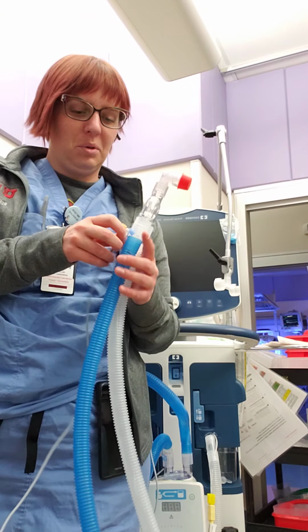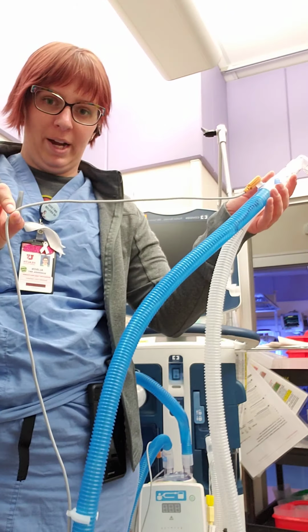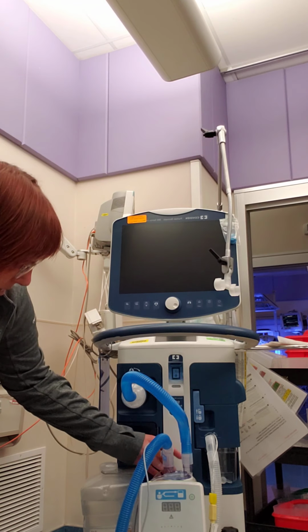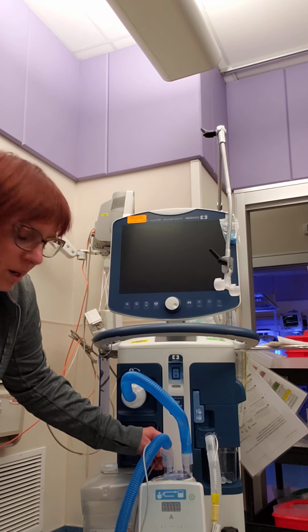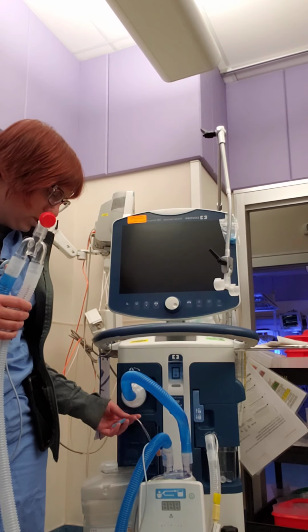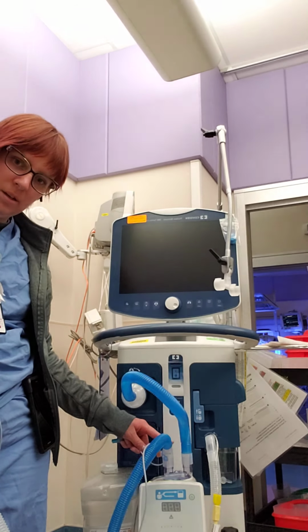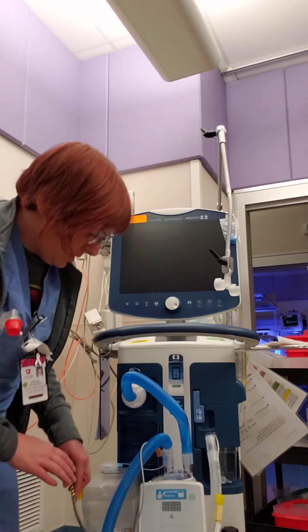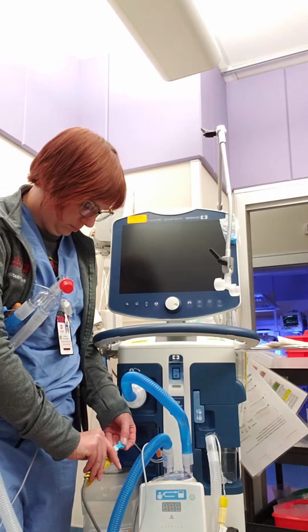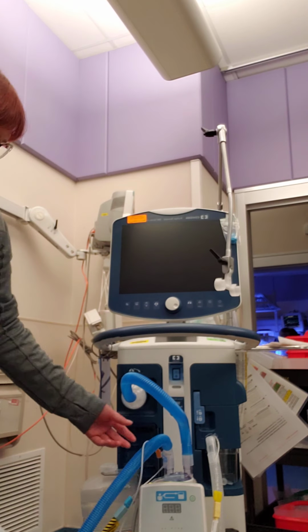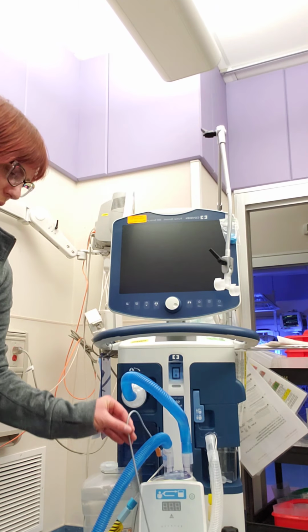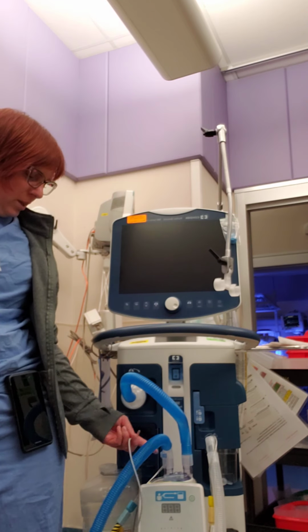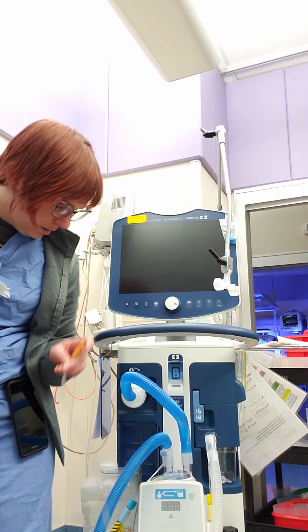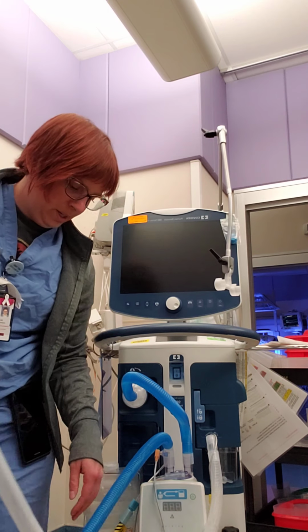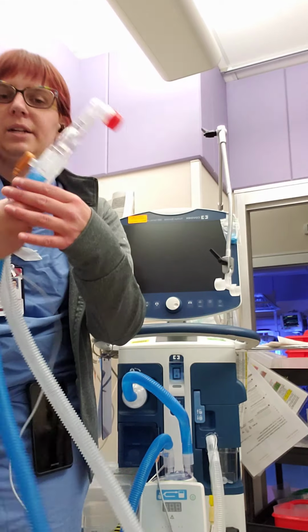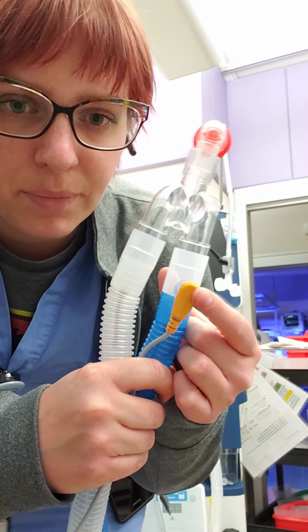One thing that's huge, and sometimes will give you problems, is the heater wires, which are wonderful. Let me show you. These attach to the heater because it's ran by the heater, and they're also attached to the ventilator circuits. So one connects to the back right here by the heater, and basically it's just matching colors. So blue to blue, and then follow the circuits. This is with the conchas. So this short piece attaches to this heater probe. There's a little hole here, and you attach the heater probe here. And then there's a longer piece that attaches up here at the Y, so we can tell what temperature is occurring right by the patient.